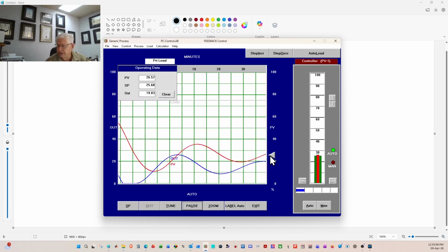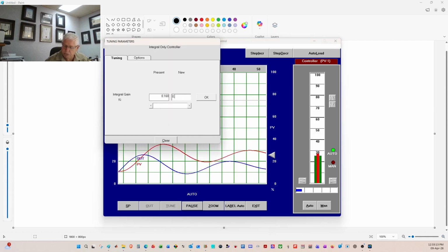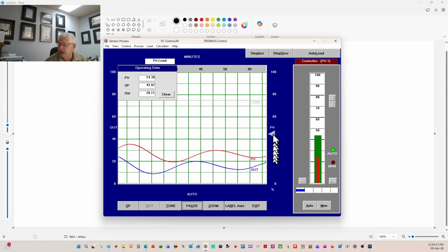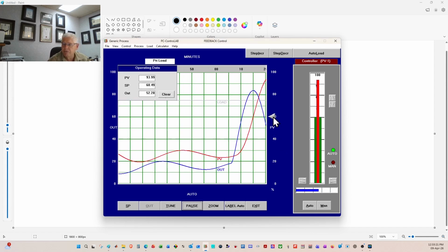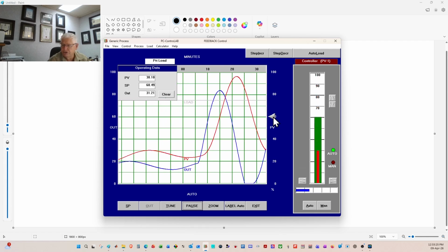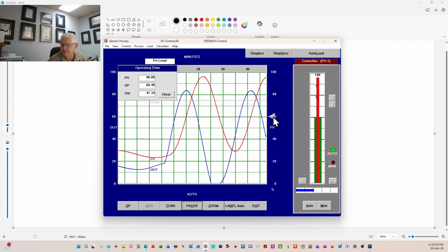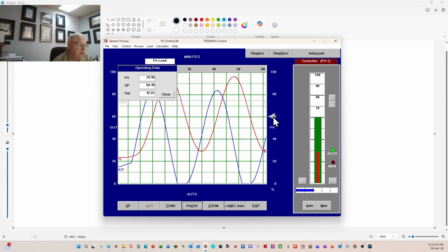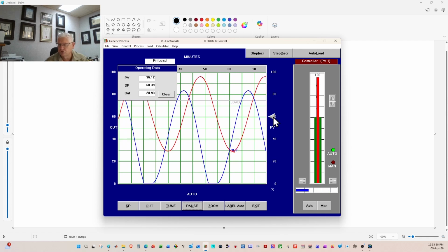And maybe just for my last demonstration, let's take that up to 0.32, and we'll change the set point up to about 60%. You can see how fast it's responding now, and of course have a look at that process of mine. The process is rather oscillatory. I just want to see if it's going to pretty much stay the same. And if I was to make the value even bigger than that, my process would be totally out of control.